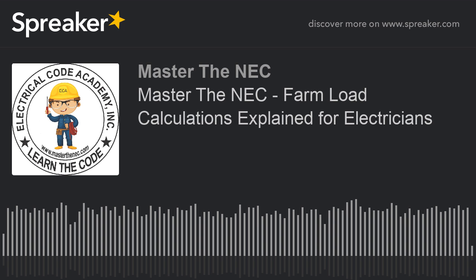Now, here's where it gets a little bit trickier, but I don't think so when you see the context behind it. It says, where the dwelling has electric heat and the farm, and that's anywhere on the farm, has electric grain drying systems, then Part 4 of this article shall not be used for calculating the dwelling load, where the dwelling and farm loads are supplied by a common service.